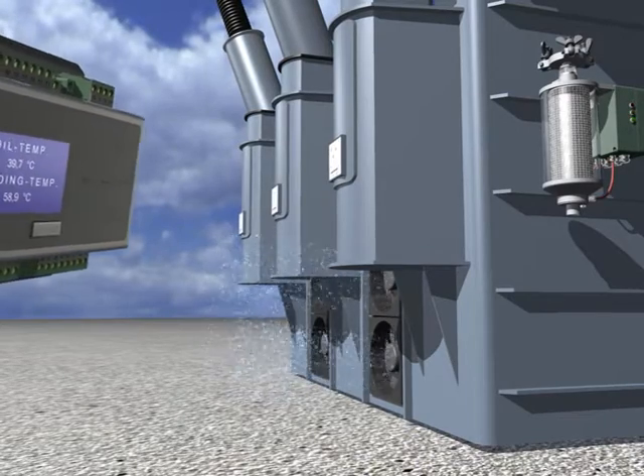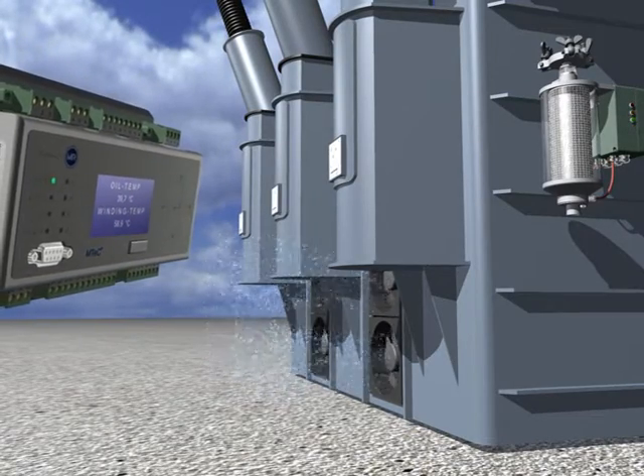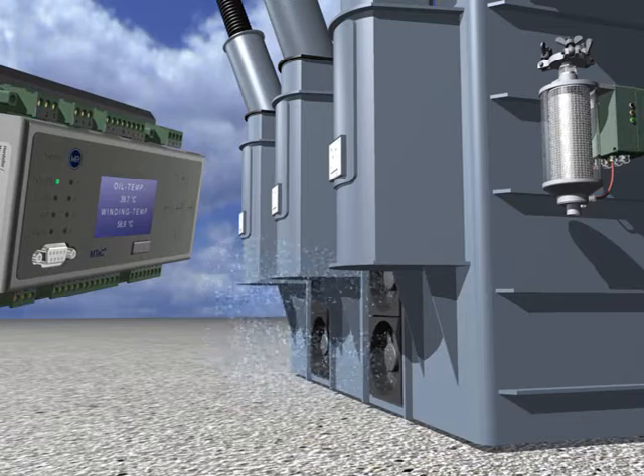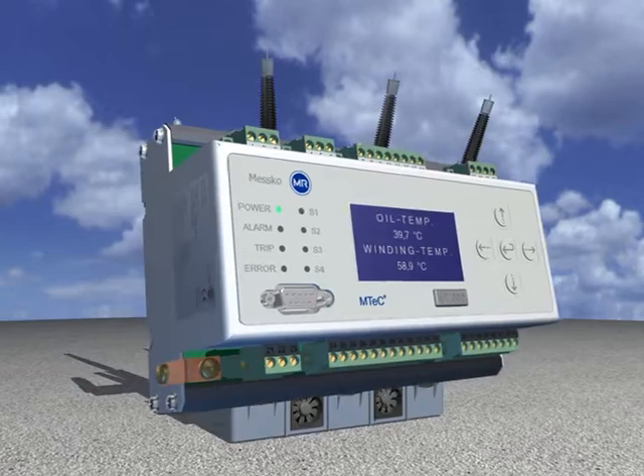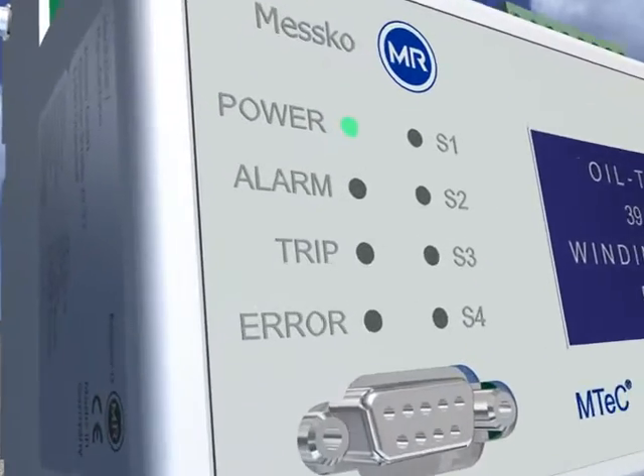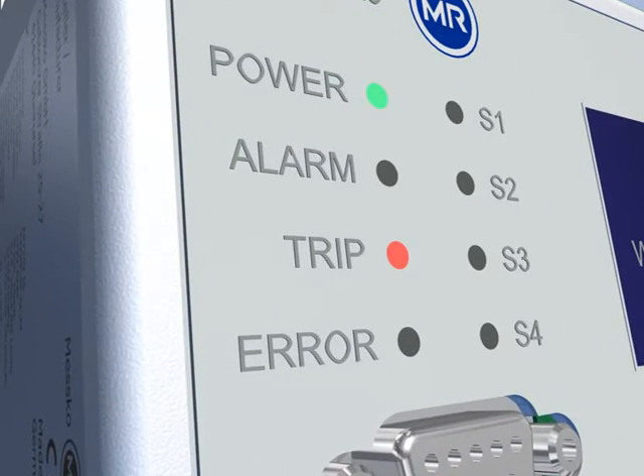The lifespan of your transformer depends to a great extent on thermal aging of the insulation materials. The MTeC calculates for you the percentage of lifespan which has already been used. The most important functions on the device, such as power, alarm, trip, error, and the operational state of the individual fan groups, can be seen at a glance on the LEDs.